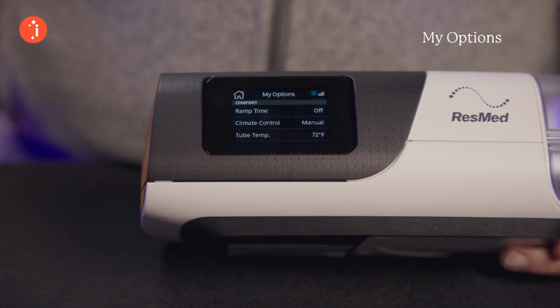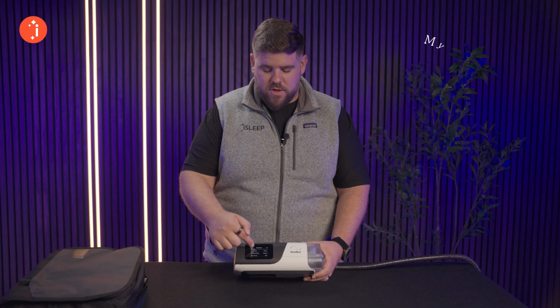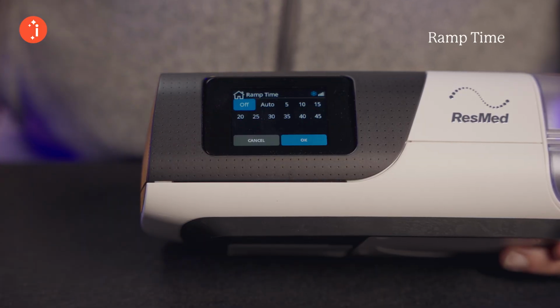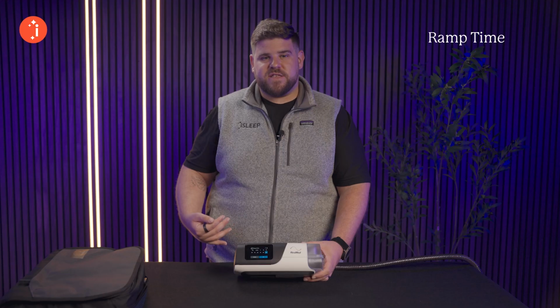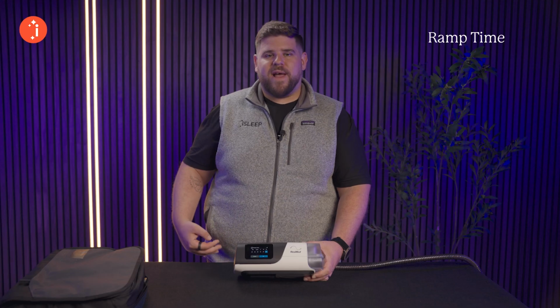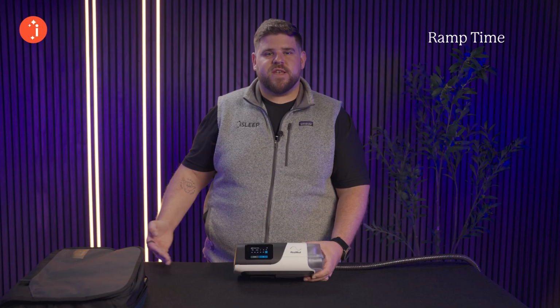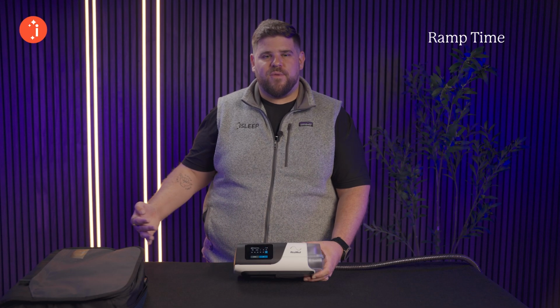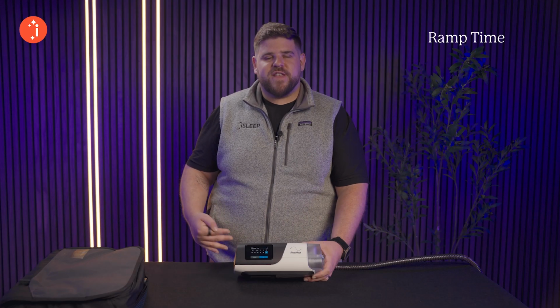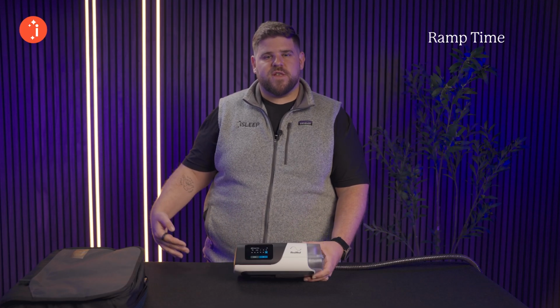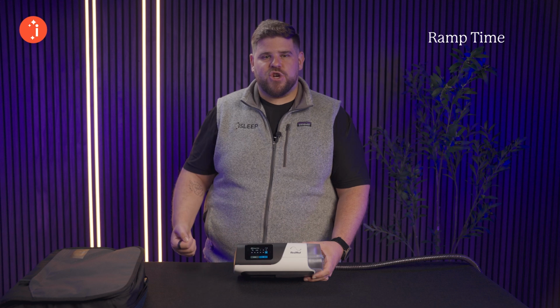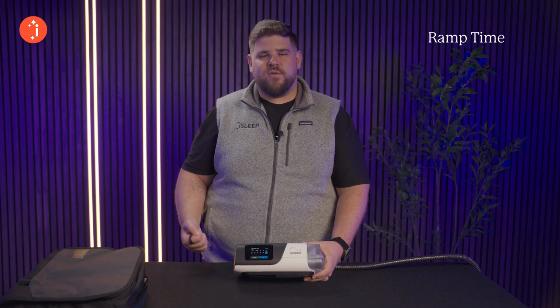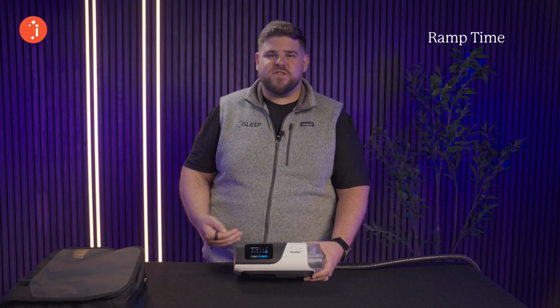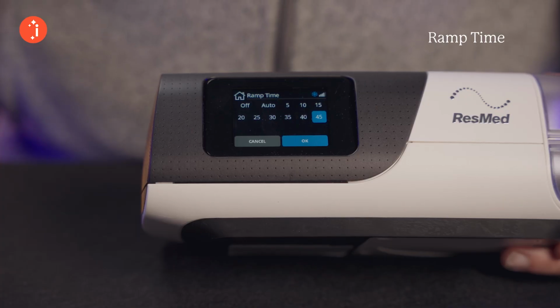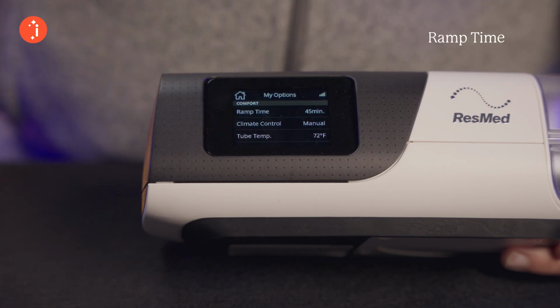The first thing you'll see is ramp time, which is totally adjustable—anywhere from off to auto to 5 minutes all the way to 45 minutes. Ramp gives you an opportunity to fall asleep before the pressure rises all the way to your therapeutic setting. So if you're on a pressure of 10 or 15 and find it hard to fall asleep, you can enable ramp, and it will start the pressure low, around 4 or 5 centimeters, then slowly increase over the selected time period. Once you select what's comfortable, click OK, and it'll take you right back to the main menu.